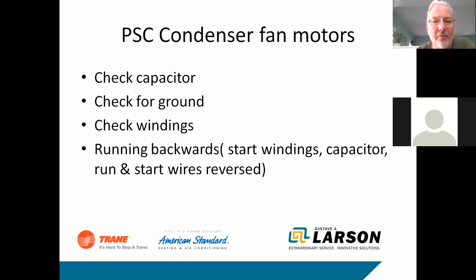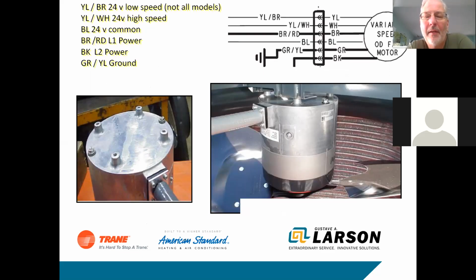One of the things I get a lot of calls on is the condensers. We've got PSC motors for condenser fans, and we've got ECM motors. The ECM motors are pretty simply regulated. It's an ECM motor, but we're using a simple 24-volt signal. On some of the older equipment, we actually had two-speed motors, a high and a low speed. On the new stuff, we don't do that anymore. We just have one speed.